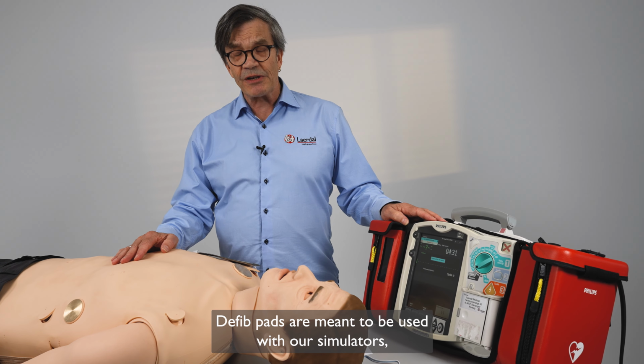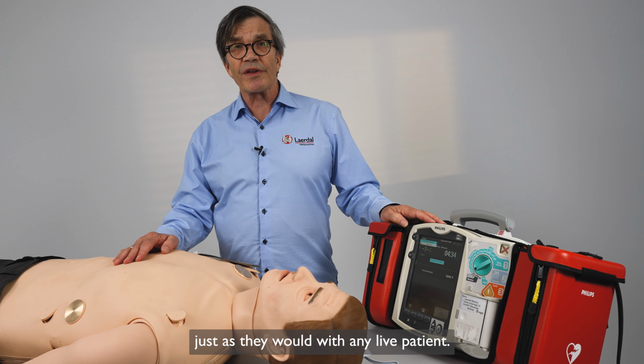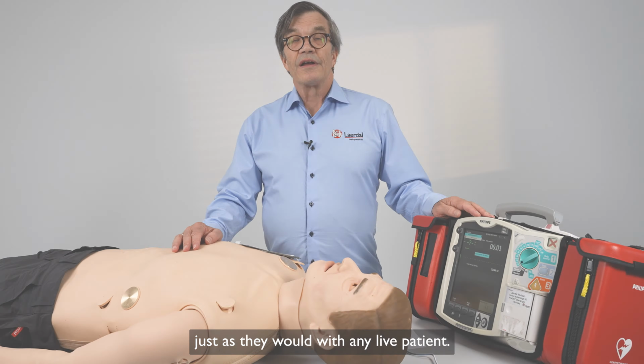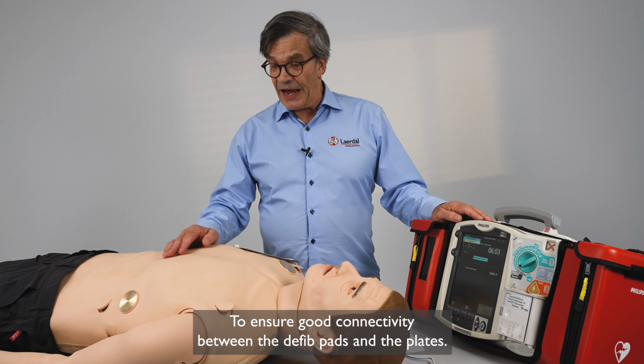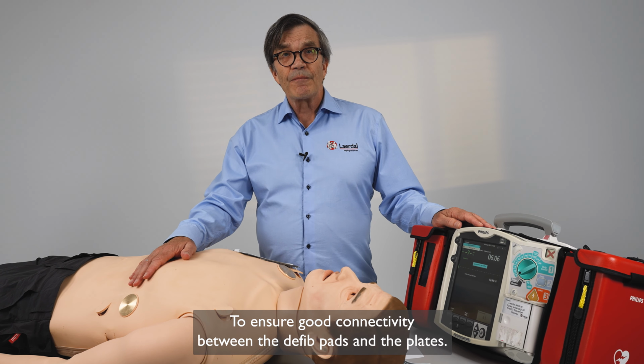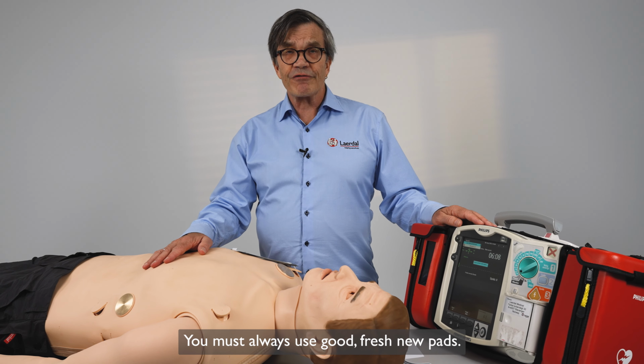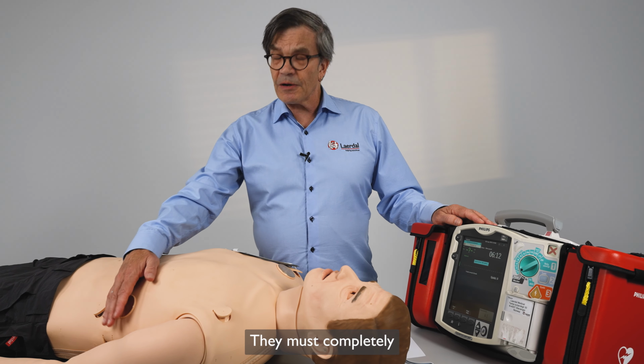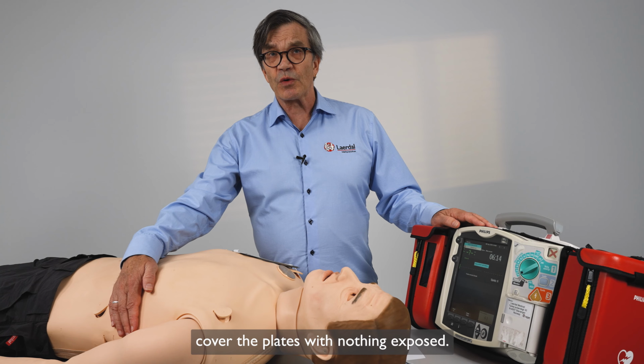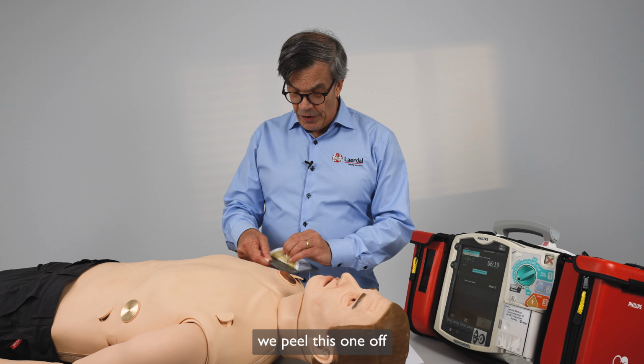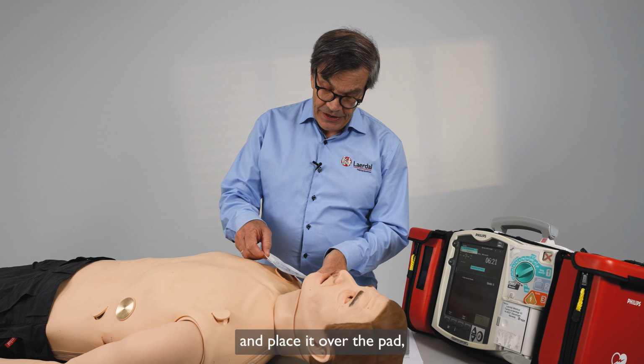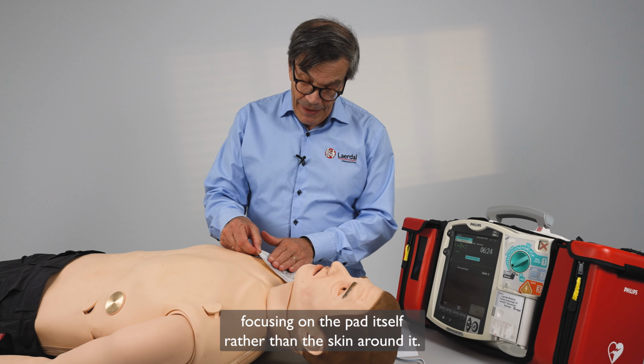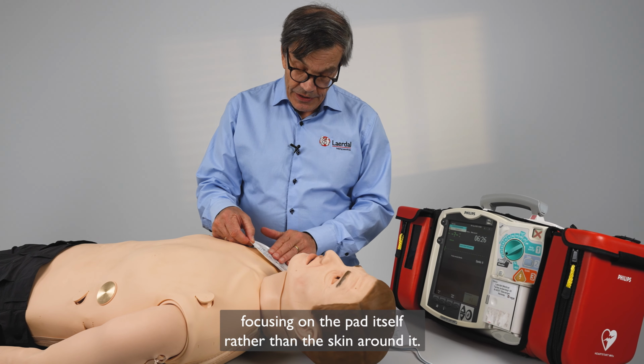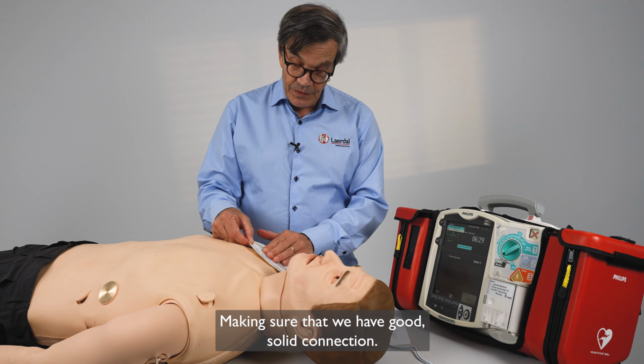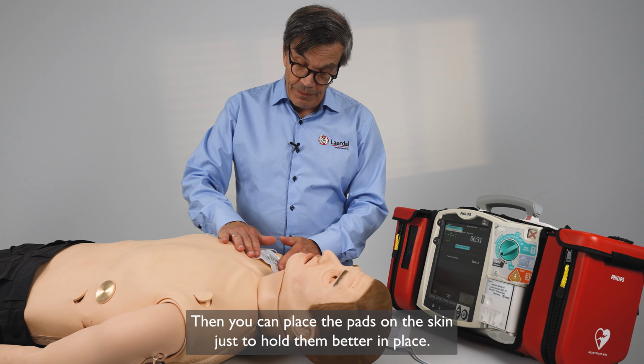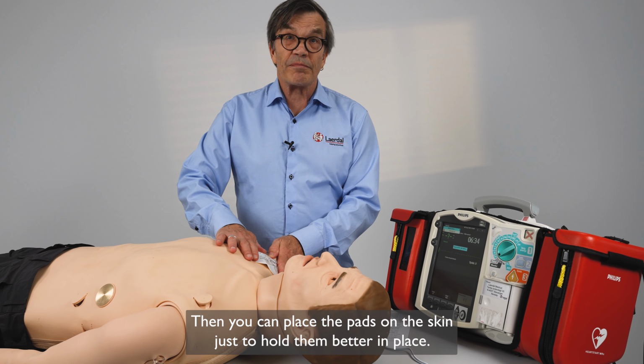Defib pads are meant to be used with our simulators, just as they would with any live patient. To ensure good connectivity between the defib pads and the plates, you always use good, fresh, new pads. They must completely cover the plates with nothing exposed. For example, we would peel this one off and place it over the plate, focusing on the pad itself rather than the skin around it, making sure that we have good, solid connection. Then you can place the pads on the skin just to hold them better in place.